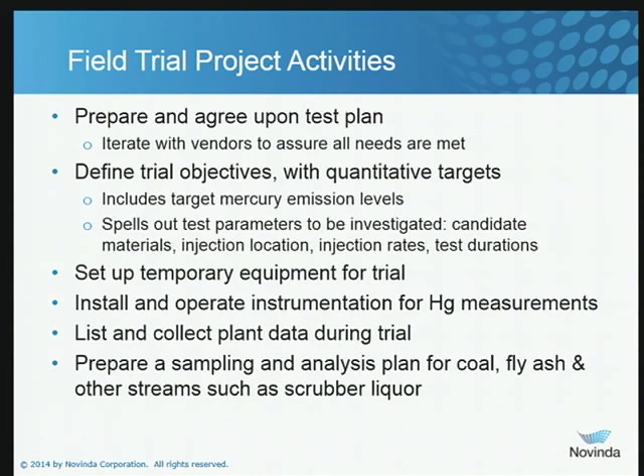You want to make sure that the vendors you think you're going to use are available and can provide the services you need. Especially this summer, there's a lot of testing activity going on and availability is going to be a real challenge. Once you have your trial objectives, make certain you include quantitative targets so that your test team knows what they're aiming for. For example, MATS is 1.2 pounds per trillion BTUs. A lot of plants are saying they want to be at one pound per trillion BTU or less to make certain they are below the limit. So if you've got a margin of safety you want built into your test plan, make certain that is explicitly noted in the documents so that everybody knows the targets they're shooting for.